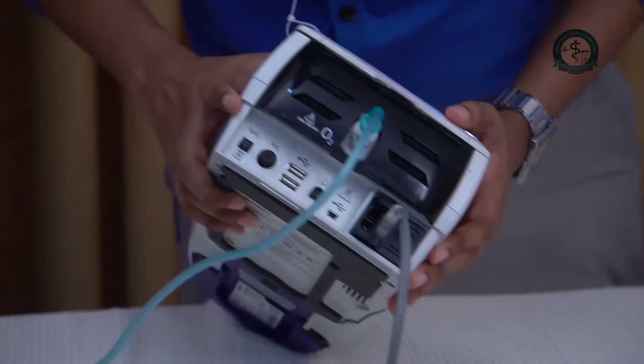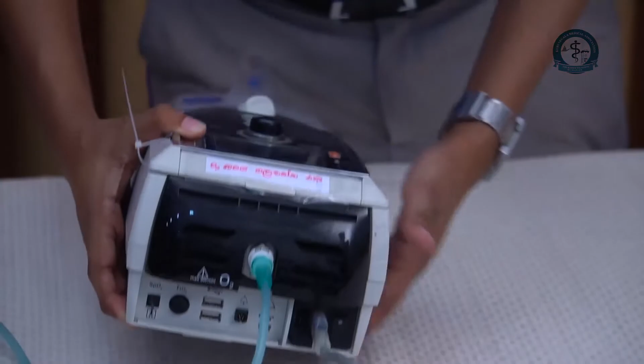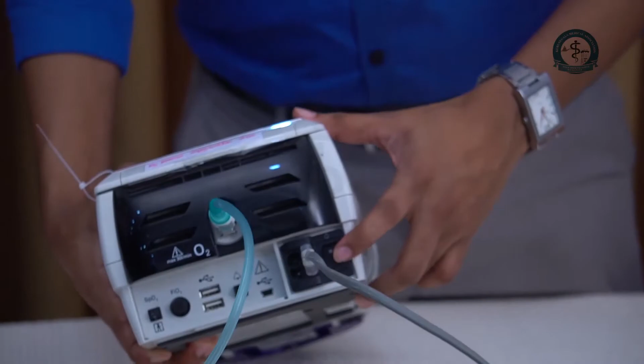Main unit. The main unit is powered by an AC current or an inbuilt battery. However, it is advisable to connect to the mains using the supplied power cable. The rear surface of the main unit contains several connection ports and a switch. 1. Oxygen connection port. This is an easily damageable piece and should be handled with care. It is better not to detach it from the main unit. The oxygen source should be connected to this port by a tube.